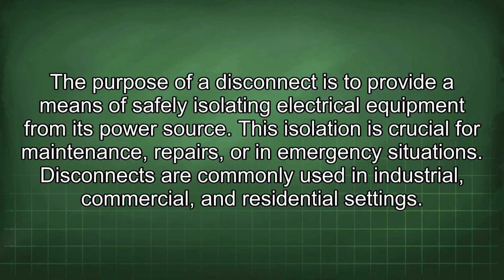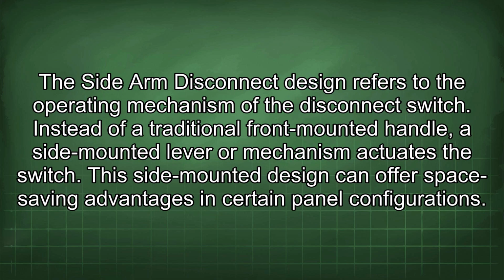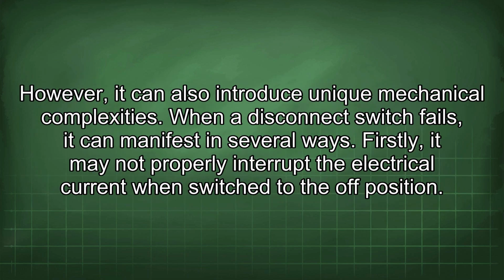The purpose of a disconnect is to provide a means of safely isolating electrical equipment from its power source. This isolation is crucial for maintenance, repairs, or in emergency situations. Disconnects are commonly used in industrial, commercial, and residential settings. The sidearm disconnect design refers to the operating mechanism of the disconnect switch. Instead of a traditional front-mounted handle, a side-mounted lever or mechanism actuates the switch. This side-mounted design can offer space-saving advantages in certain panel configurations. However, it can also introduce unique mechanical complexities.